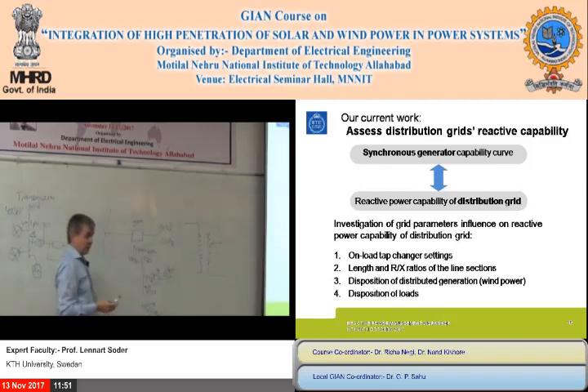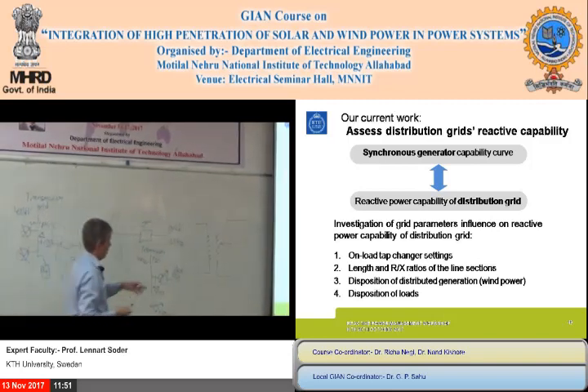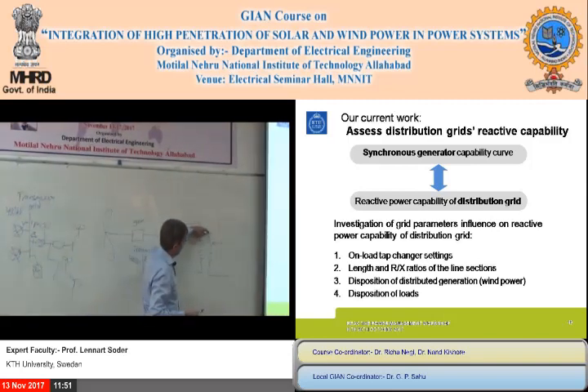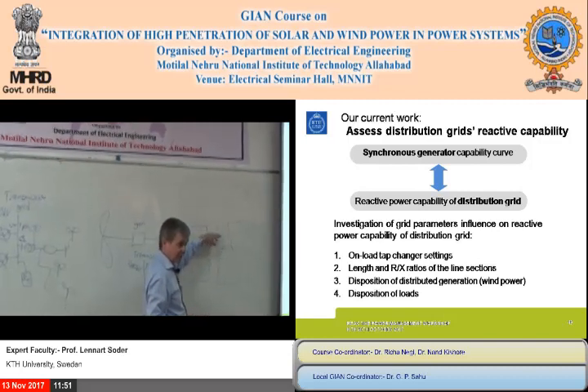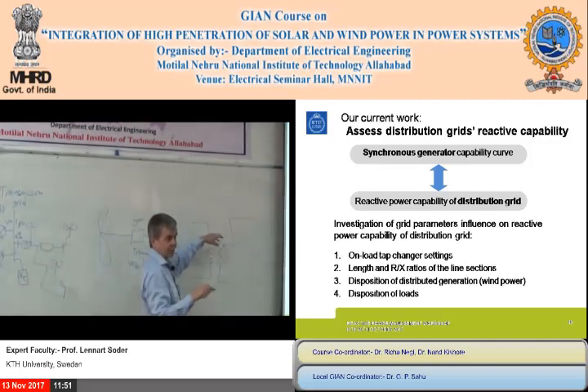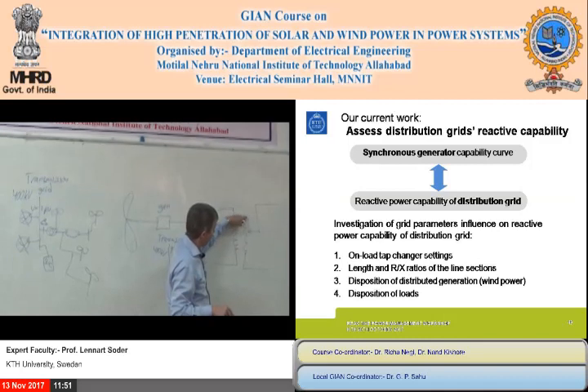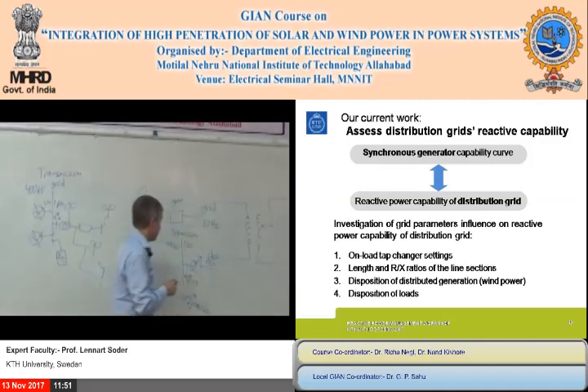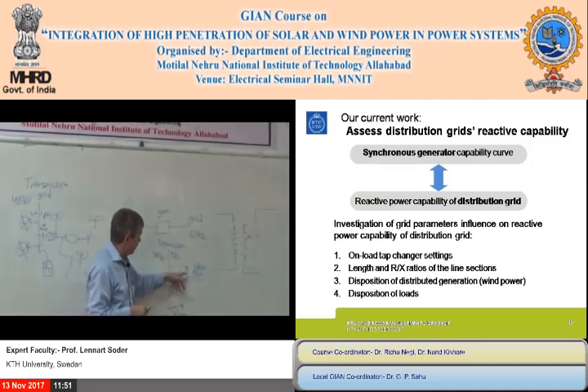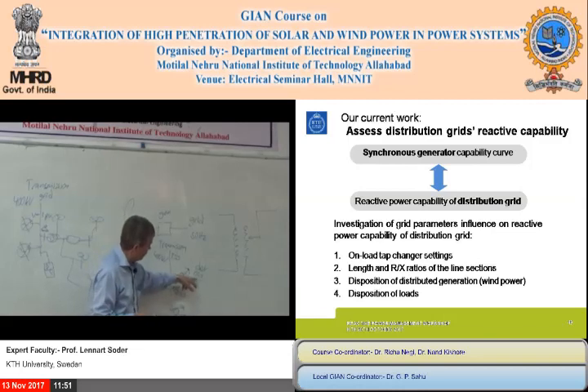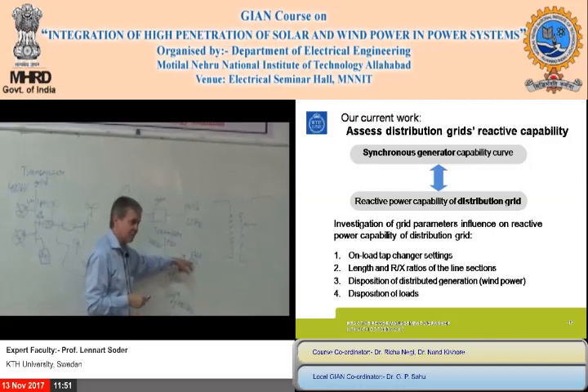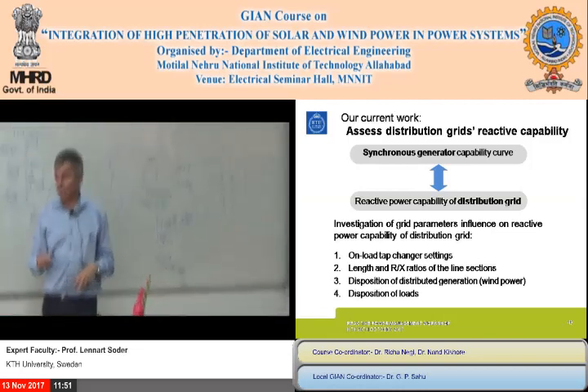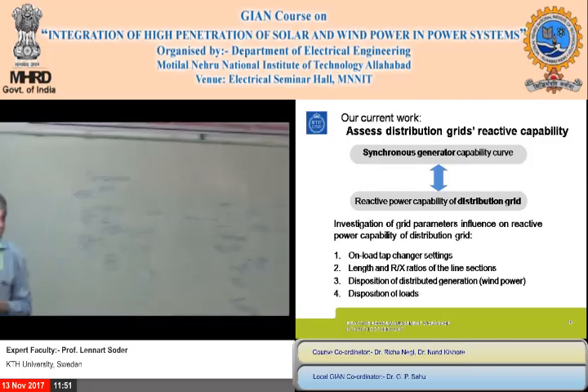You can decide on the secondary side if you should have a high voltage or a low voltage. This is controllable in steps, normally some percent, on the secondary side. This affects the voltage in the distribution system, and also has an effect on the reactive capability.